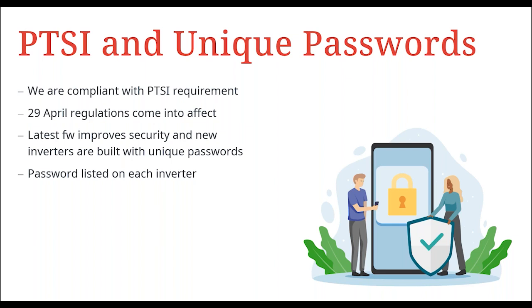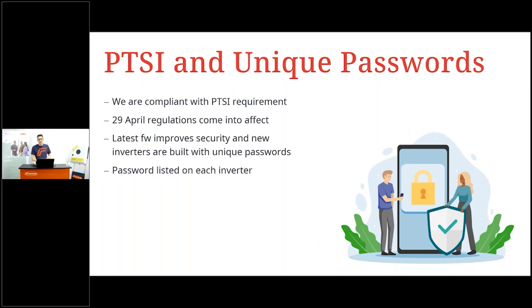The other important update this month is that we will start to see unique passwords for the Wi-Fi access point on the inverters. So when you're commissioning a new inverter, you access the Wi-Fi access point with your phone or with your laptop to communicate with it directly. Up until now, we've used the password 12345678. In future, for regulatory requirements, we will need to use a unique password for each individual Gen24. So that password will in future be printed on the side of the inverter. Where you currently find the nameplate of the device, you'll also find the unique password listed. So make sure to take details of that. If you're struggling to connect to your inverter, it's probably because you're using the wrong password.